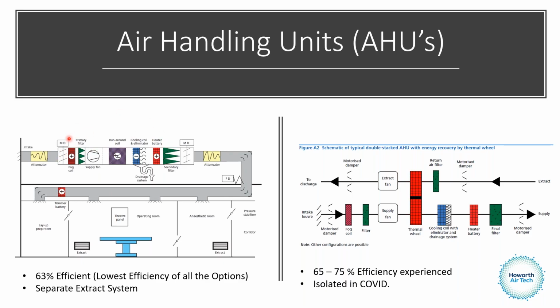We have motorised dampers that sit at each end of the air handling unit, and the frost coil has been changed to a fog. We have a primary filter, then the supply fan, the runaround coil, and the cooling coil sits on the discharge side of the fan to keep it under positive pressure, so any water that comes off won't pool but go through the drainage system, then the reheat battery, final filter, and damper. This method of heat recovery is the least efficient, around 63%, as it'd be an extract system across the other side of the plant room, giving heat recovery back to this unit.